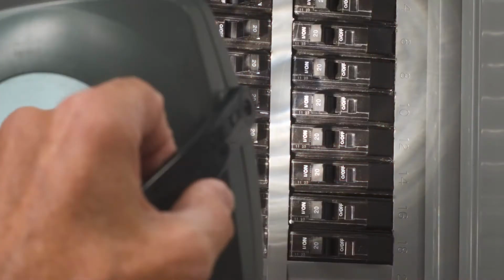It really, really is prudent to pay an electrician to come in and take the panel apart. I don't know what they're going to charge, maybe $100, $80. It's going to take them like 20, 30 minutes. Make sure there's no double taps, there's no covers missing, anything like that in there.